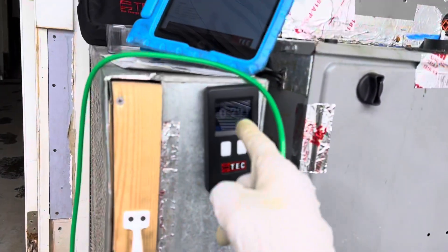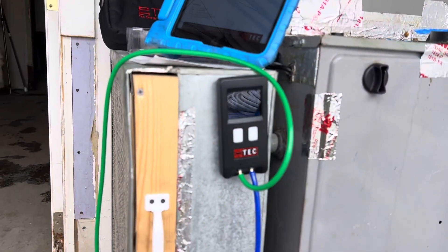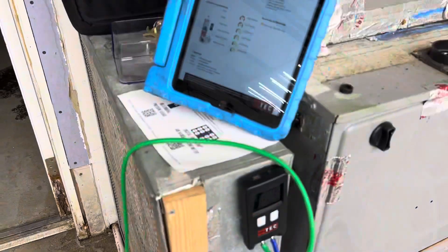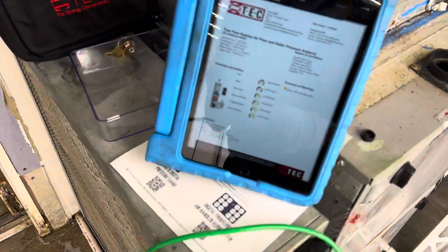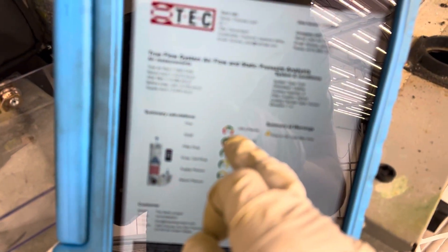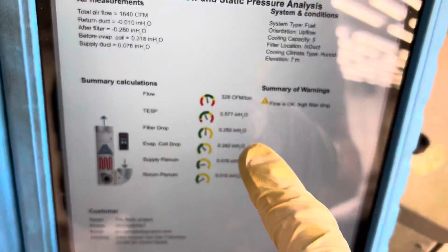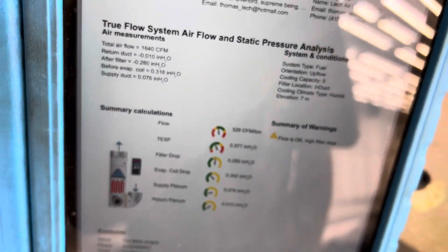Now we know we're restrictive. According to this we're only doing 328 CFM per ton, which is way on the low side. But we are in a room that's high humidity, like 80% humidity, so we do need that low run for dehumidification, but not that low.